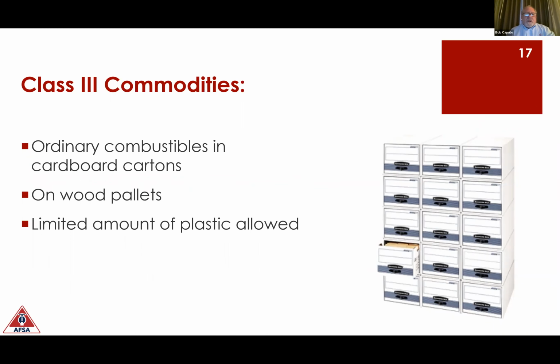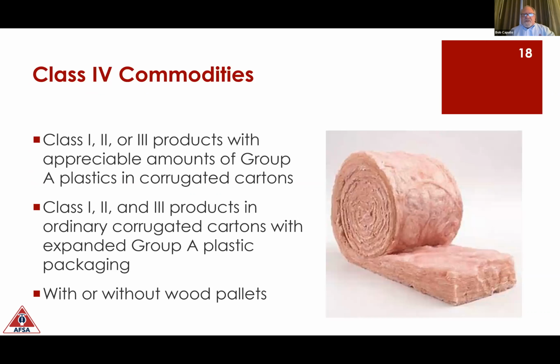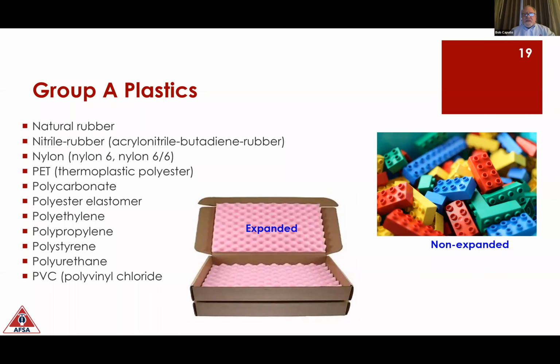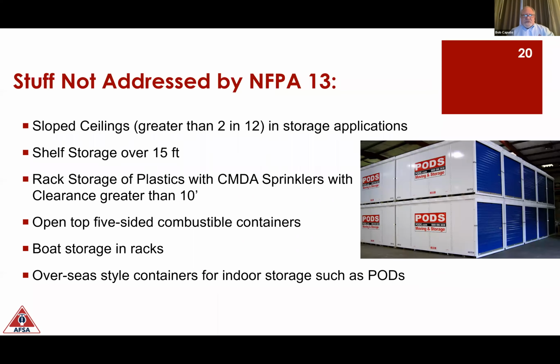Class 3 commodities are ordinary combustibles in cardboard boxes or on wood pallets with a limited amount of plastic. Class 4 products are all of the prior products, but now there's a more substantial amount of Group A plastic packaging or within the product itself. And then, of course, I have all these Group A plastics, again, expanded and non-expanded. So natural rubber, nitrile rubber, nylon, but anything that says poly something is going to be a Group A plastic. Very few tenants don't have Group A plastics. So the higher the classification, the more heat release rate I get. So the more robust my fire sprinkler system needs to be.